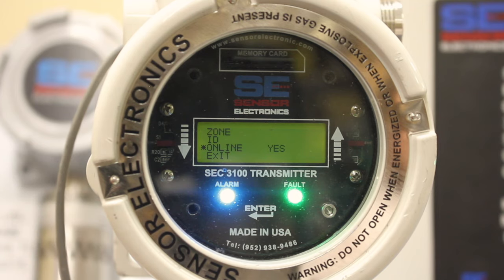Online is if you want to take the sensor off the data highway network. So typically it's set for yes, so it'll talk to the 3500 controller, but if you want to take it offline for some reason, you just select no, and now it'll turn itself off and it won't communicate back to the 3500 controller.